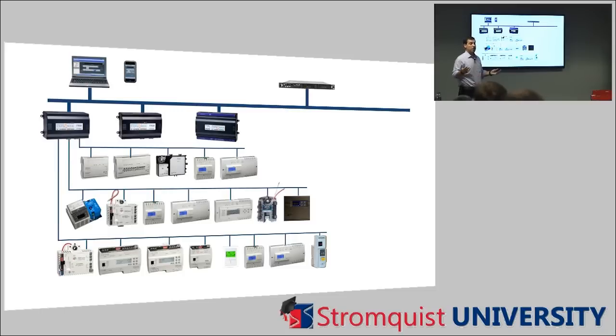So the reason that you end up having more than one Jace almost always is because you've filled up that one Jace with as much as you can possibly do. So then you just add another Jace, and eventually these would be wired in and go up into a supervisor, which is basically like a master Jace, no matter if it's different companies coming in and putting in their products.